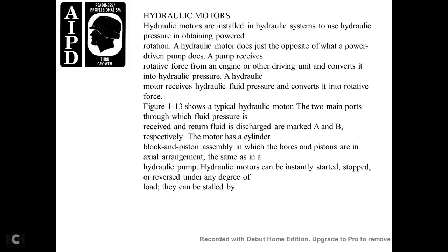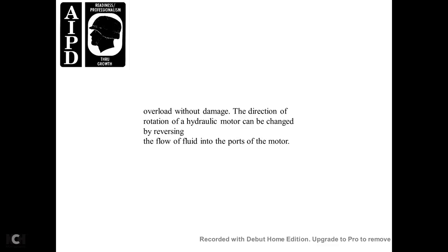Hydraulic Motors. Hydraulic motors are installed in the hydraulic system to use hydraulic pressure to obtain rotational power. The hydraulic motor is essentially the opposite of the power-driven pump: a pump receives mechanical force from an engine and converts it into hydraulic pressure, while a hydraulic motor receives hydraulic pressure and converts it into rotational force. Figure 1-13 shows a typical hydraulic motor, with two main ports through which fluid is admitted from the pressure side and returned from the discharge side, marked A and B respectively. The motor's cylinder block and piston assembly are in an axial arrangement, the same as in the hydraulic pump.